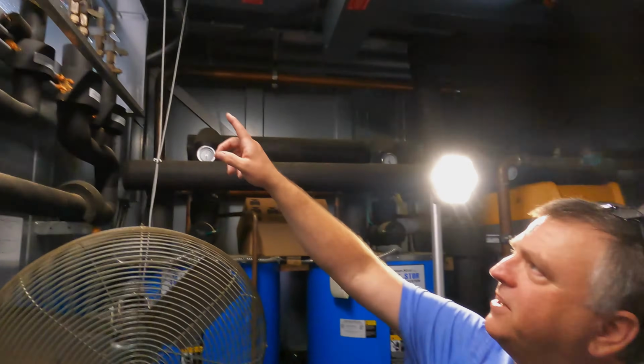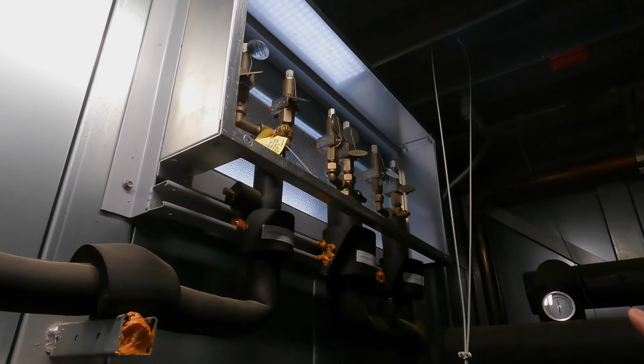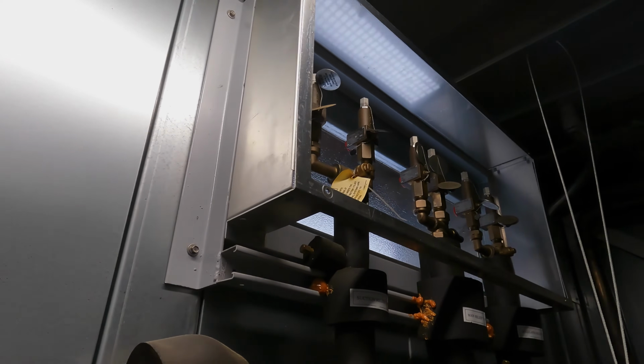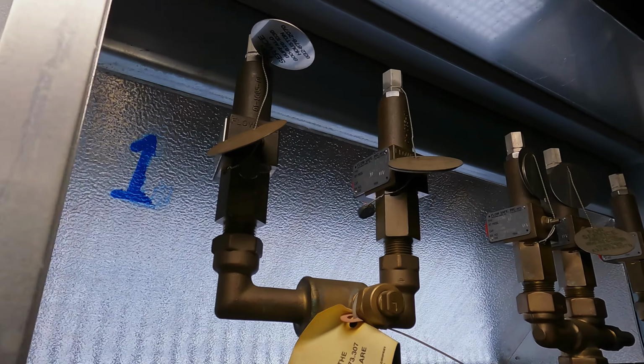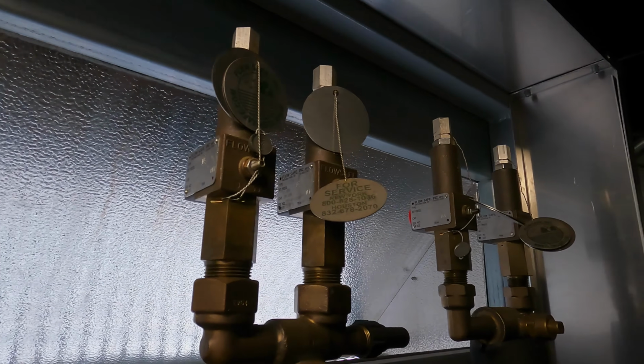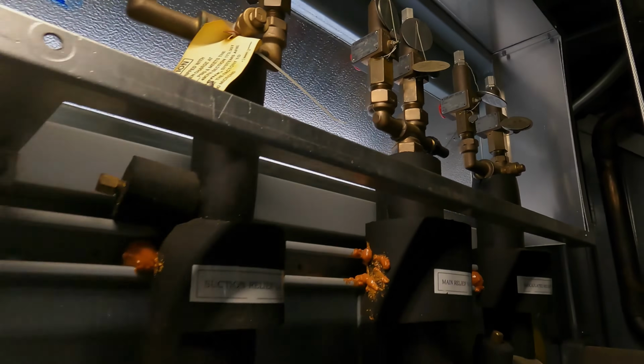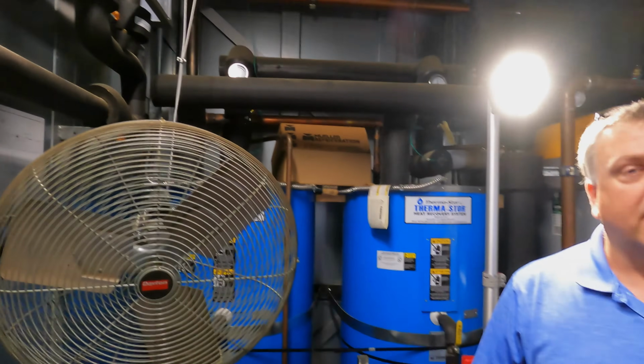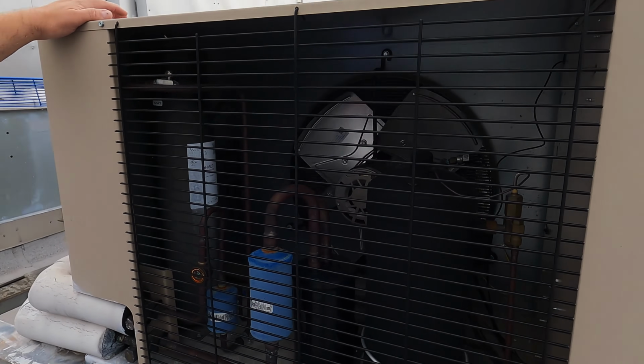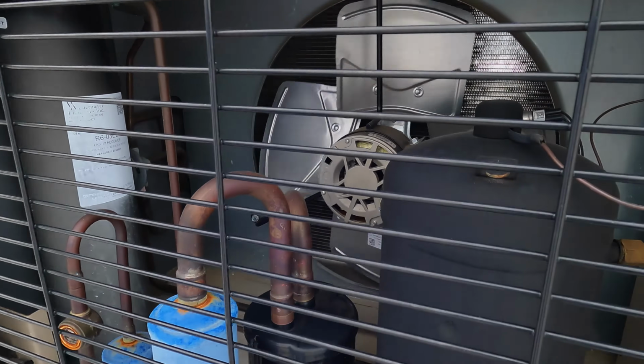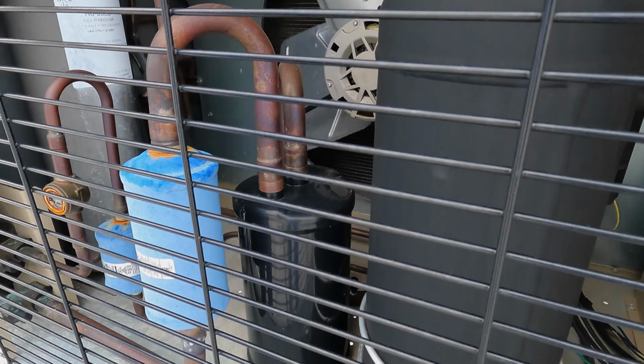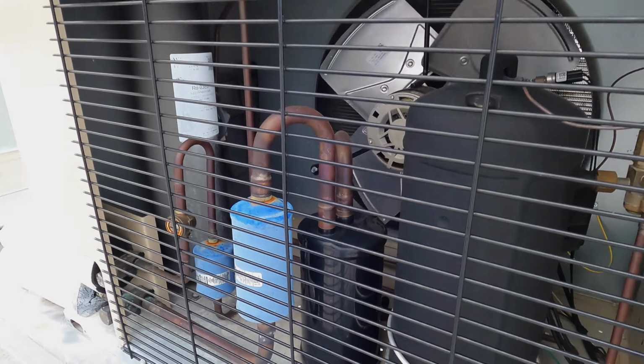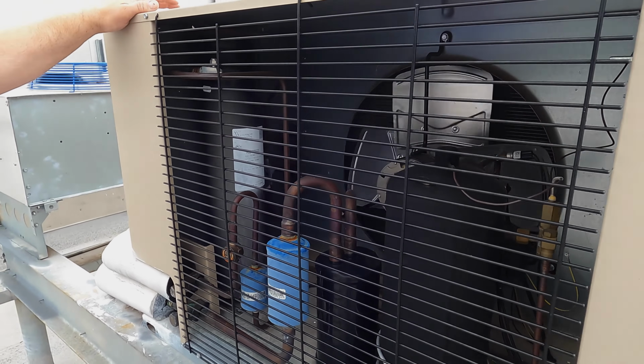I took the panel off so you guys can see it. That's our relief valves up there. Our highest one is 650 pounds. So if we get over 650 pounds on our main relief valve, we're going to pop off and start losing CO2. Well, guess what? When the power goes out, I don't have anything cooling it, so it's going to want to do that. So what they've done is they incorporated an auxiliary unit to control our CO2 vessel to keep the pressure low so we don't lose any CO2.